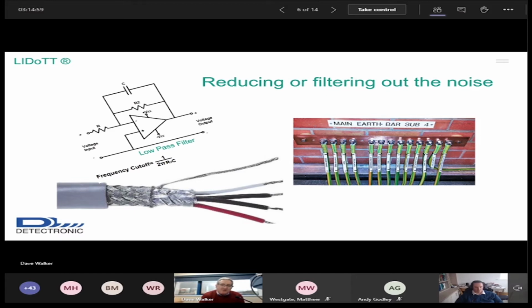Again, I'm showing the earth bar there. It's extremely important to make sure that you've got an adequate earth supply. And that might be, if you're in a rural area, driving in not just one earth spike, but you may need up to 4 earth spikes.